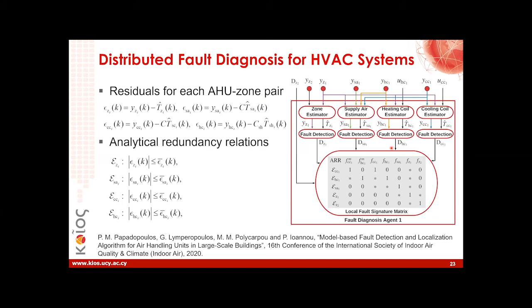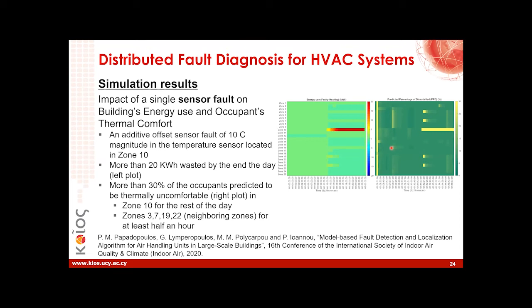This is an important area. For example, when we simulated a 10-degree magnitude sensor fault in zone 10 in this benchmark problem with 25 zones, not only did we have significant energy wasted in that zone, but also the comfort of other areas that are interconnected to that area were affected.